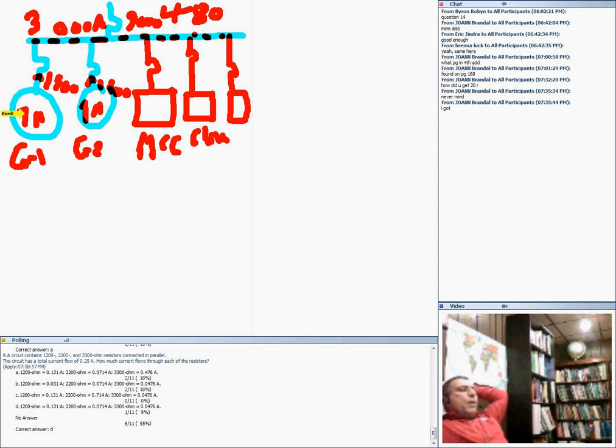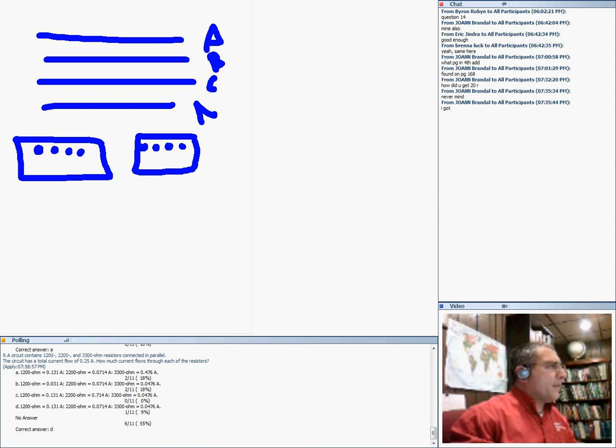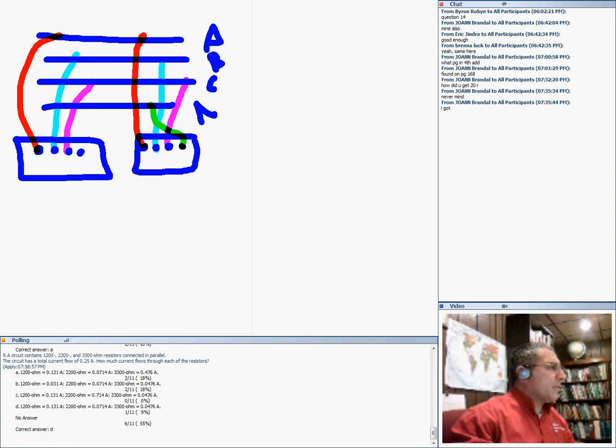And, my friend, physically, mechanically, guys, when they tie them, here is phase A, here is phase B, here is phase C, and this is my neutral. These are the terminals of this generator, A, B, C, and the neutral, terminals 1, 2, 3, 4 of generator number 1. What you do is physically take phase A from this side to phase A from the other side, and the same thing for phase B. Can you guys see how they are parallel, tied together at the other end? And phase C from this side to this side, and the neutral is tied from this side to the neutral from the other side. That's what it means.